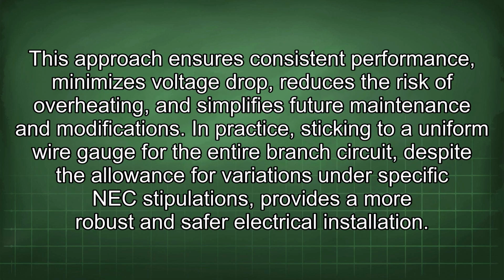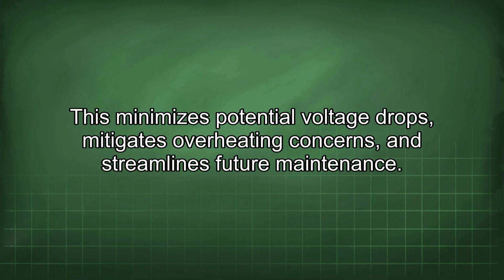This approach ensures consistent performance, minimizes voltage drop, reduces the risk of overheating, and simplifies future maintenance and modifications. In practice, sticking to a uniform wire gauge for the entire branch circuit, despite the allowance for variations under specific NEC stipulations, provides a more robust and safer electrical installation. This minimizes potential voltage drops, mitigates overheating concerns, and streamlines future maintenance.